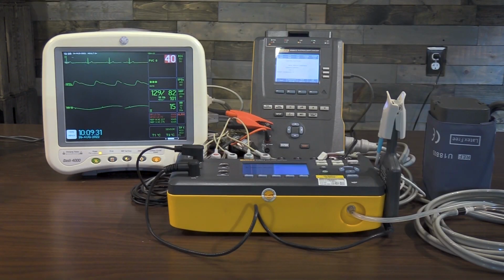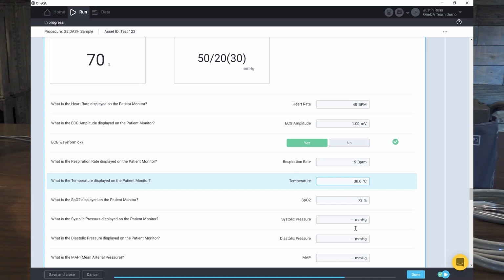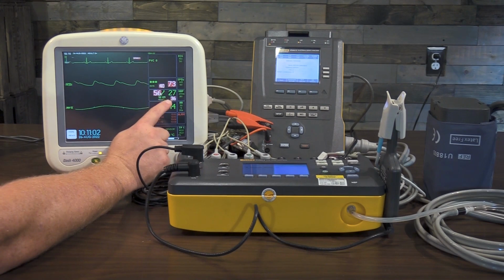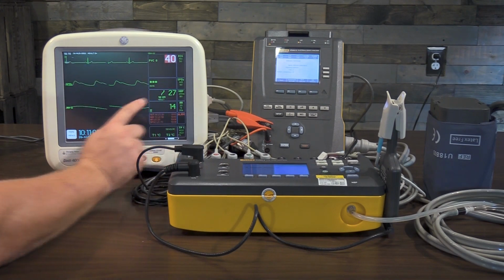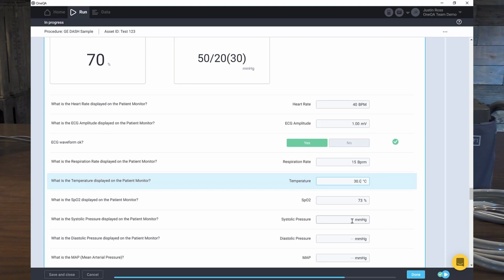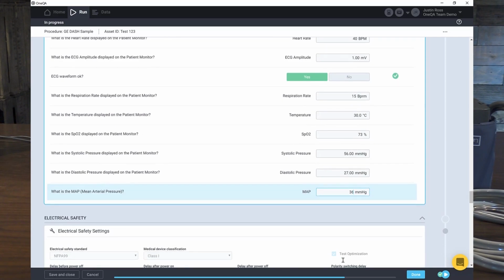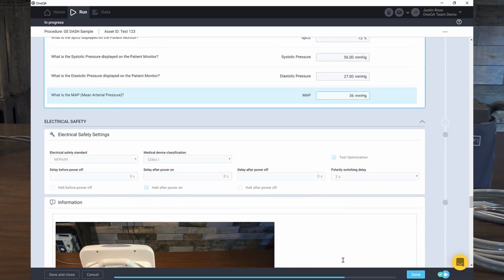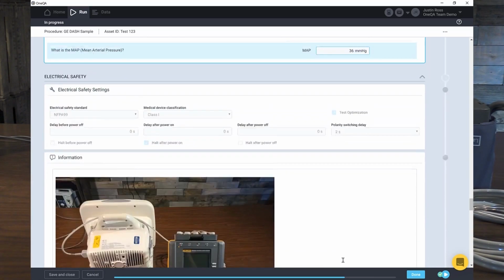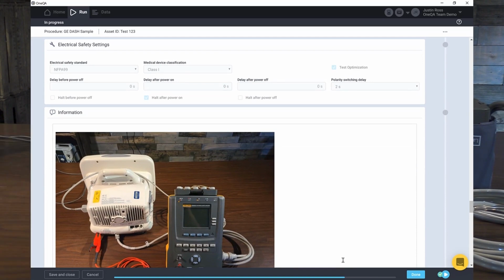And my blood pressure. All right, here we go. And our alarm, we're now at 56 over 27 with a mean of 36, which puts us out of tolerance. And the alarm went off, so let's go ahead and we'll set this at 56, 27, and 36. All right, we did all those parameters without having to touch the ProSim 8. So now we can roll right into our electrical safety test. So you'll see, silence that so we can hear better.